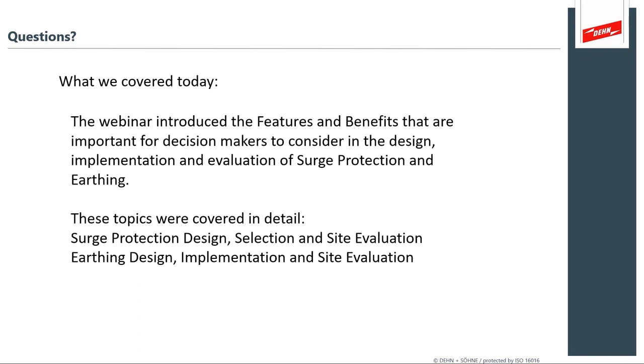And so DEHN SPDs offer excellent diagnostic features on the AC power and data products. What is generally expected is after severe lightning storms, you want to go through your plant and evaluate if your surge protectors have experienced damage. Basically, the DEHN products are designed to release themselves after they've experienced failure so that they don't sit on the AC power. So after a heavy lightning event, you will want to evaluate your SPDs.